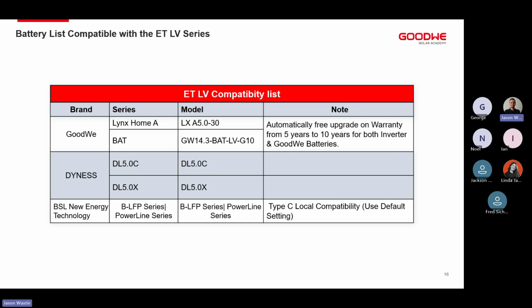Our Type A battery list is all of our international battery brands. That is where we do full-on international battery compatibility testing and line-by-line protocol testing. Meaning Dyness, for example, we will send an inverter to Dyness, Dyness will send a battery to GoodWe, and both R&D centers will match the protocol line by line. When doing the configuration on the system and you set the communication up for the battery, we will select Dyness DL5.0C, and it will then be able to communicate directly with the battery. Other batteries, we will use our default setting.